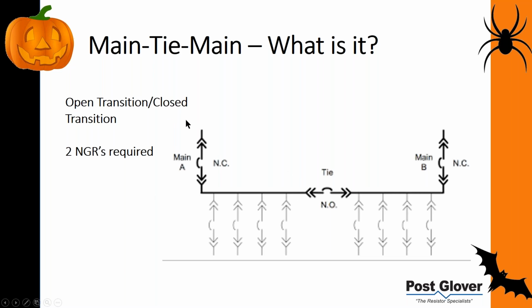Essentially, once you have this issue, when you're trying to get back up and running—say your main A is now ready to operate—with an open transition, you're temporarily closing this and opening that, which means these loads are going to be briefly out of service while this is coming back on. So it's an open transition: you're not sharing the system, but you're going to have a brief disconnection.